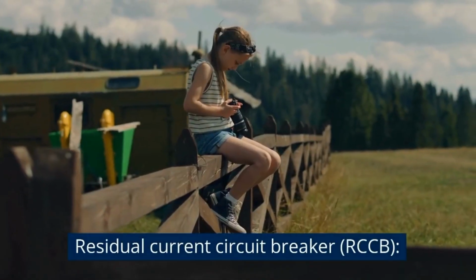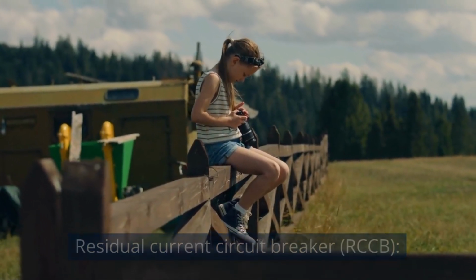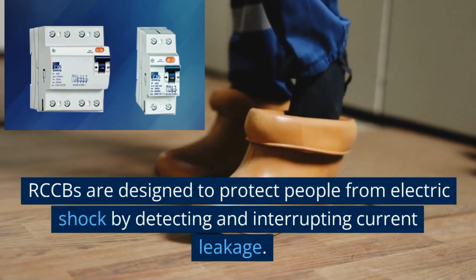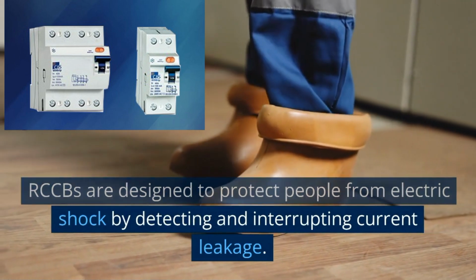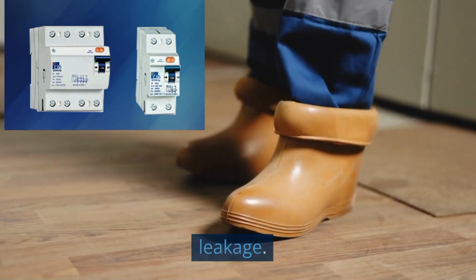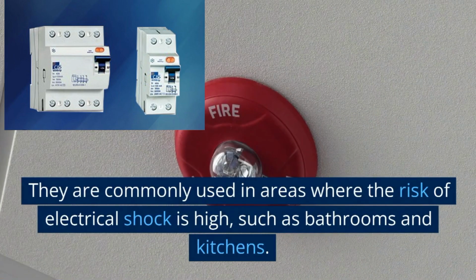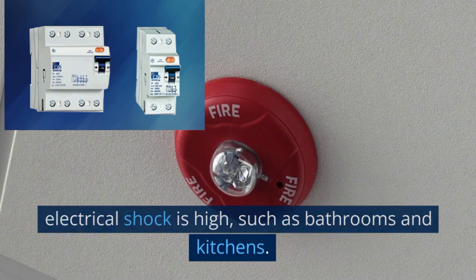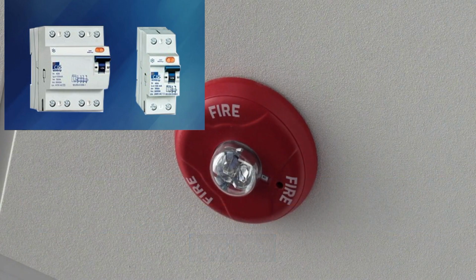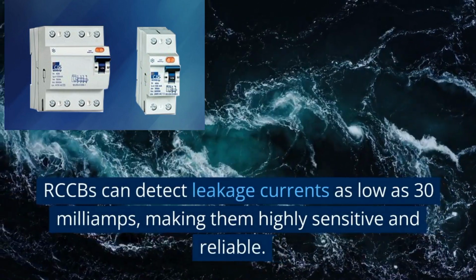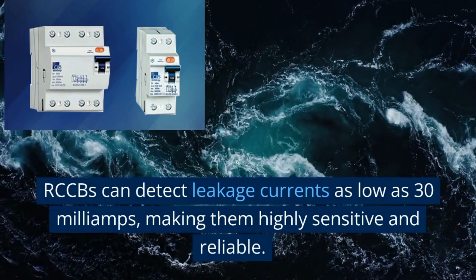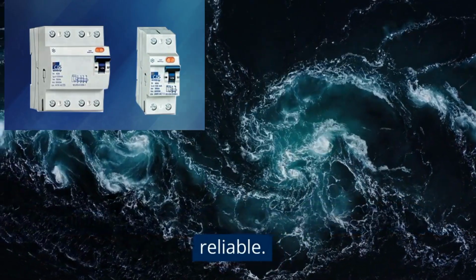Residual current circuit breaker, RCCB. RCCBs are designed to protect people from electric shock by detecting and interrupting current leakage. They are commonly used in areas where the risk of electrical shock is high, such as bathrooms and kitchens. RCCBs can detect leakage currents as low as 30 mA, making them highly sensitive and reliable.